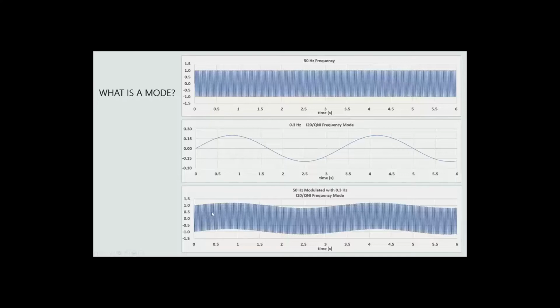What happens here is that this 50 Hertz is modulated with 0.3 Hertz, so in a way, a mode is a frequency of a frequency. So when I say the QNI mode has a frequency of around 0.3 Hertz, that only means that 0.3 Hertz modulates the 50 Hertz signal. We don't have to study 50 Hertz because we assume it to be steady, so the only thing we study in small signal software is this modulation. Hopefully that explains the mode, because I know I was confused many years ago about what these small frequencies are related to and how they relate to 50 Hertz. So for those of you who wondered, that's what it is.